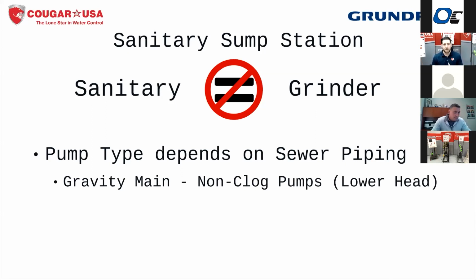So we don't want to use a grinder style pump that produces a very high head. If you do apply a grinder pumping into a gravity main, then you have a mismatch there. The grinder is going to be wanting to have back pressure against it, and there's nothing there providing that back pressure, so the pump's going to run out on its curve and potentially have conditions for cavitation or other issues, and not get a good life out of it. So anytime we're pumping into a gravity main, we're always going to recommend going with a non-clog style pump, unless there's something really bad in the water, and then we would move over to a shredder type pump, but still having that lower head requirement.